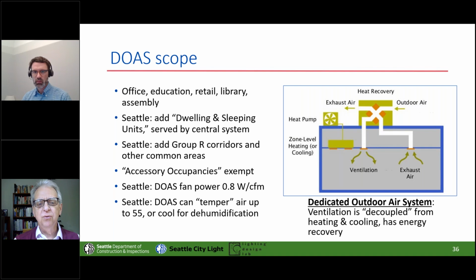There are a couple things to note there. Those last couple of bullets are that fan power is now limited to 0.8 watts per CFM. I think that came straight from a California code amendment. It was 1.0 before, right, Ben? So we're clarifying that you can temper air on the DOAS up to as much as 55, or cool it only as necessary to dehumidify.